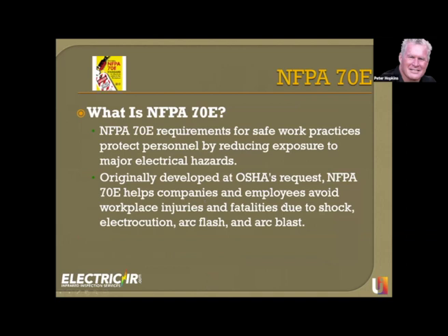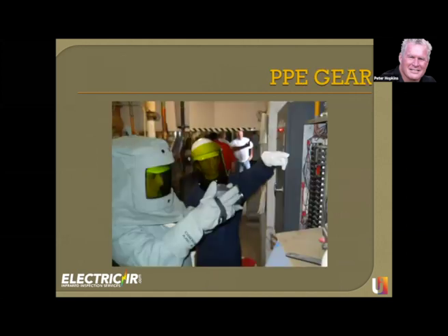So we talked about NFPA 70, which is the electrical code. 70B is maintenance and safe practices for electrical systems. Now we've got 70E, which is OSHA. 70E basically establishes the safety requirements for things like arc flash, meaning these guys need to be wearing this gear when they open and close that equipment. The training courses that teach you properly on advanced electrical will go into that.